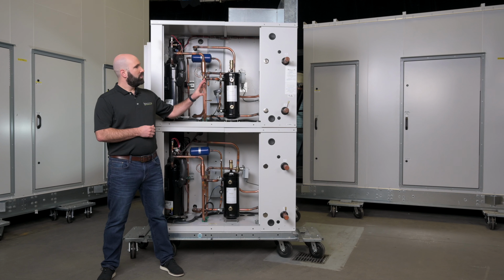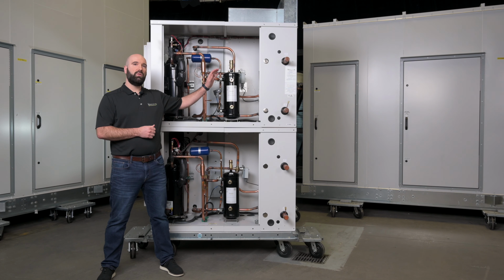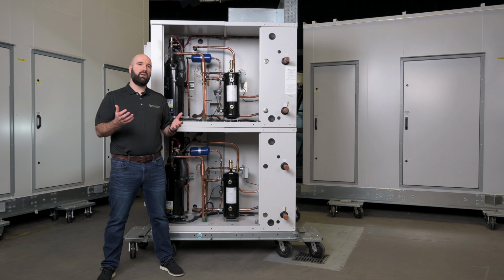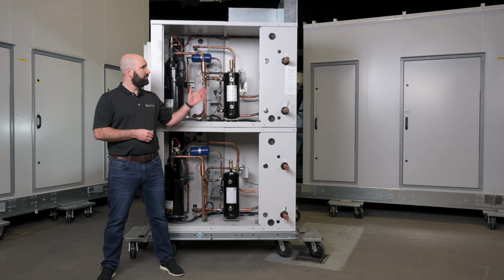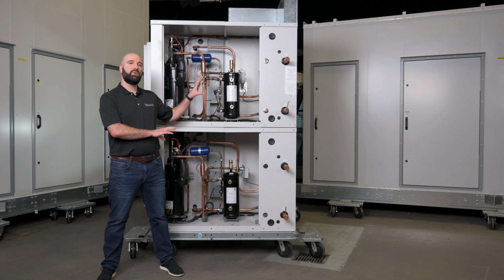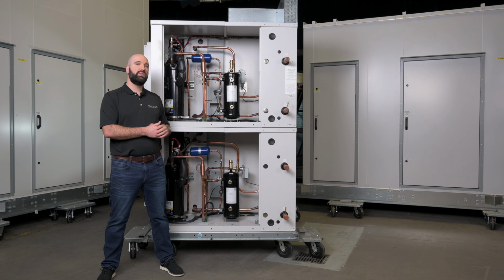And we'll take a quick look through some of the features that make these so important, so special for this space. Starting with here, the compressor deck. You've got the flat plate heat exchanger and the water connections. Again, we invite you to watch the dry cooler video, talk a little bit about why we use a water loop for heat rejection, but that's on this as well. And again, those two water loops are entirely separate. Any single failure on the refrigeration side there won't affect the other system.